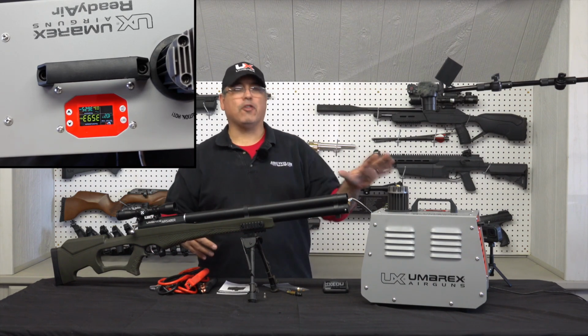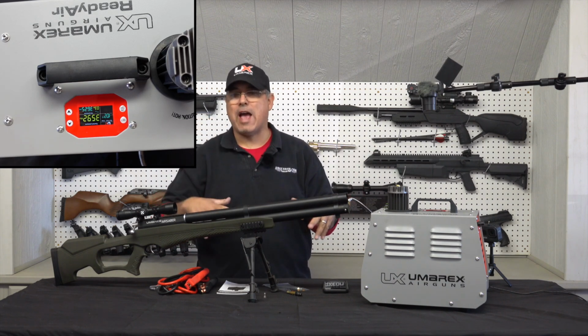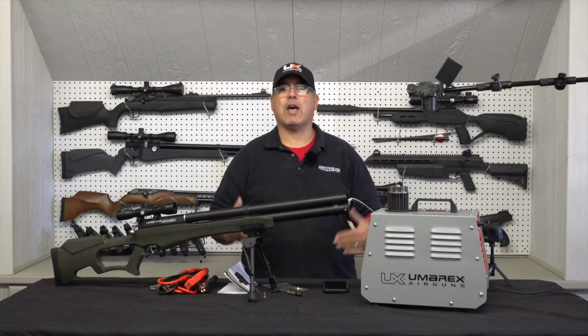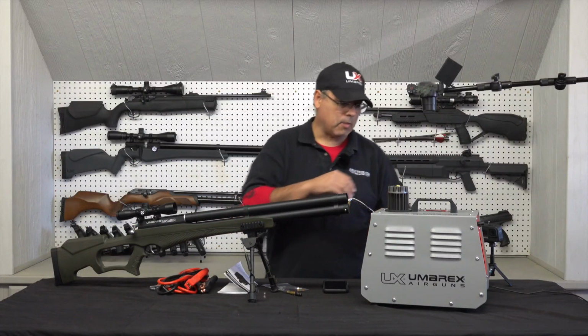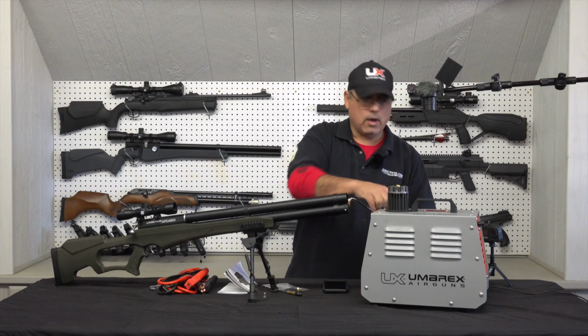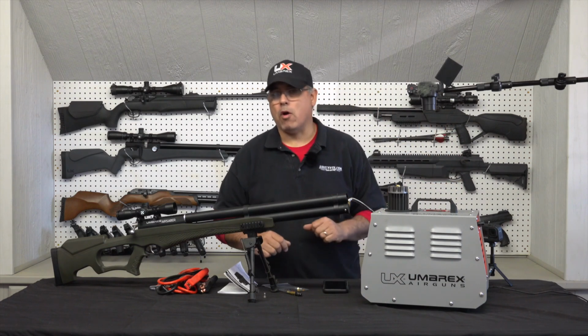Okay, so it is full, we're topped off. Those fans will continue to run until the compressor cools down to around 73 degrees. I'm gonna go ahead and bleed this off. We'll be right back. So those heavy duty cooling fans shut down at 73 degrees. We'll go ahead and unplug this now, and the compressor can go ahead and power all the way down.